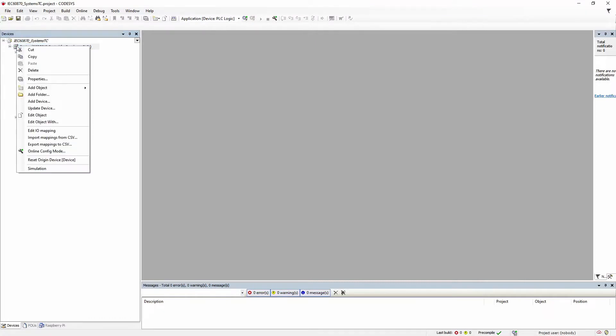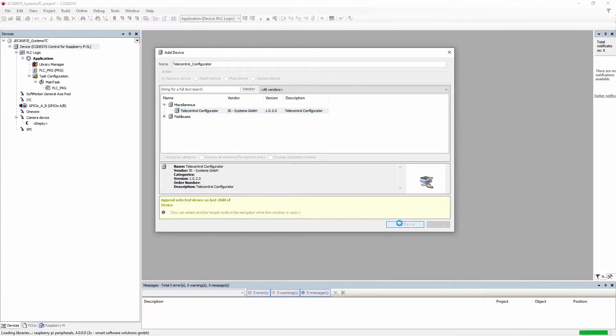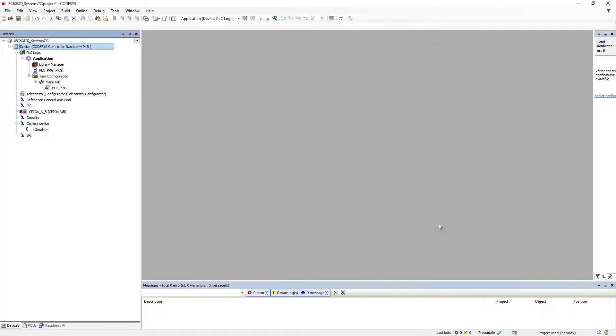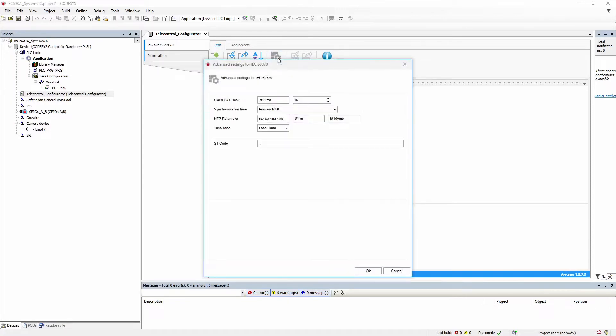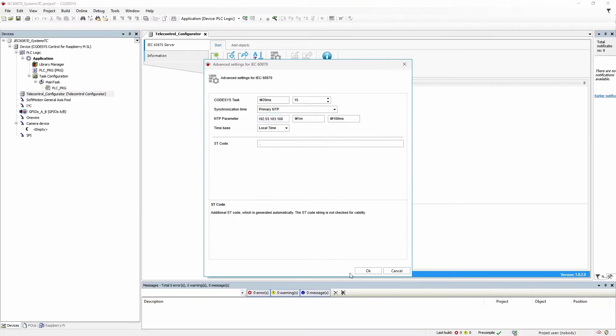3S Systems Telecontrol Package offers an efficient solution for modeling and creating a Telecontrol application by using the CodeSys PLC as IEC 60870-5-104 server, with the integration of the corresponding configurator in the CodeSys development environment as a Device Tree plugin. The advanced settings serve for the configuration of the cycle time and the priority of the generated task, the internal time synchronization of the PLC, and the insertion of additional code.